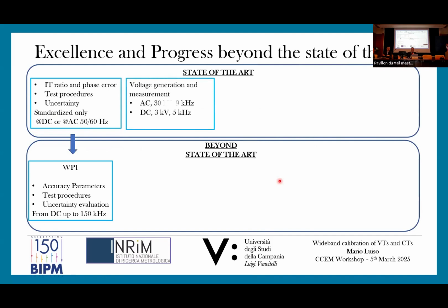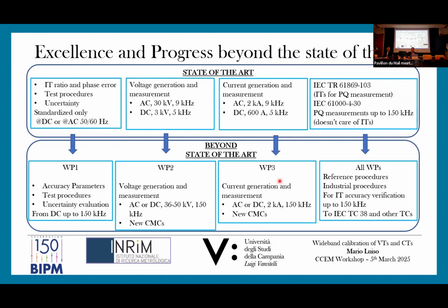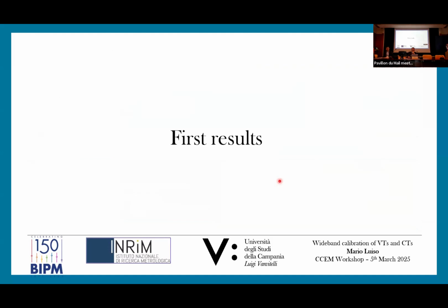Essentially, the objective of the ADMIT project is to go beyond the state of the art that currently is, I can say, represented by the IT4 PQ project. It wants to extend the findings of the IT4 PQ project to DC grids and up to 150 kilohertz. So the first results of the ADMIT project are focused essentially on the techniques for the generation of high voltages and high currents, but with reduced components up to 150 kilohertz. Differently from the IT4 PQ project, here it is difficult to reach with one single generator at the same time high voltage and high frequency. So the various partners concentrated on the use of 2 different generators to reach this kind of performance.